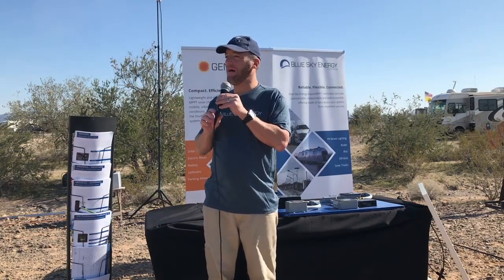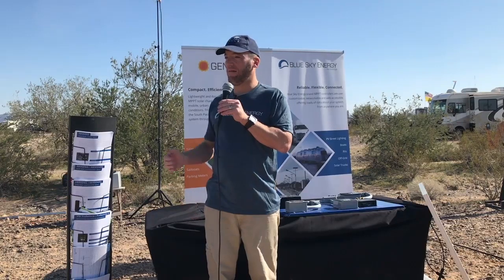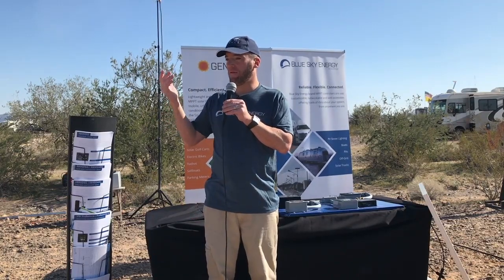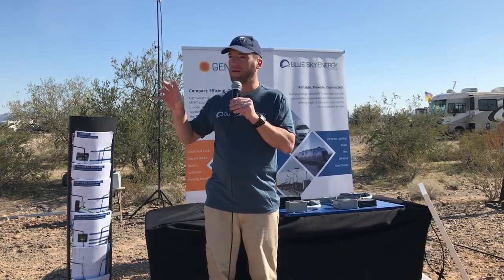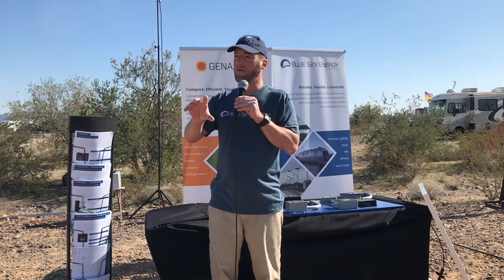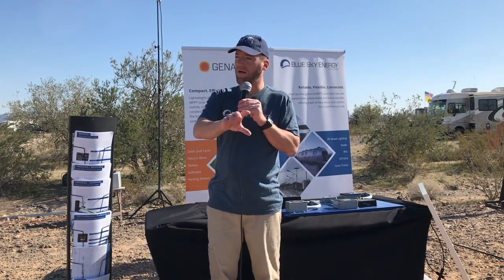So, no, you would leave it, yes, there's no reason not to. The only reason I'd say you might want to disconnect your solar is if you have a standalone controller and you're not able to program it into a storage mode charge profile, because you don't want to maintain that absorption voltage on a fully charged battery for 2 hours every day, all day, if you can help it.